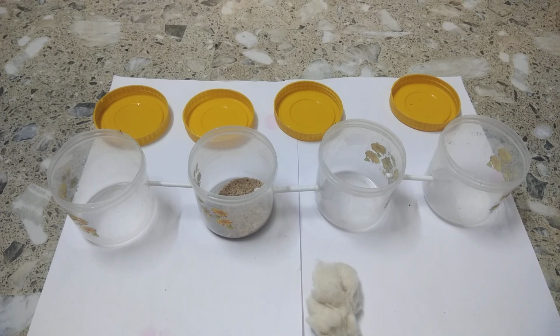The first step is coagulation. What is coagulation? Coagulation is often the first step in water treatment. During coagulation, chemicals with a positive charge are added to the water. The positive charge neutralizes the negative charge of dirt and other dissolved particles in the water. When this occurs, the particles bind with the chemicals to form slightly larger particles. Common chemicals used in this step include specific types of salts, aluminium, or iron.